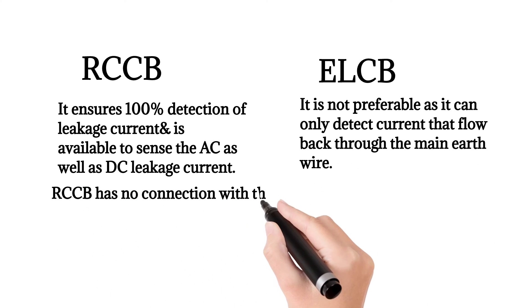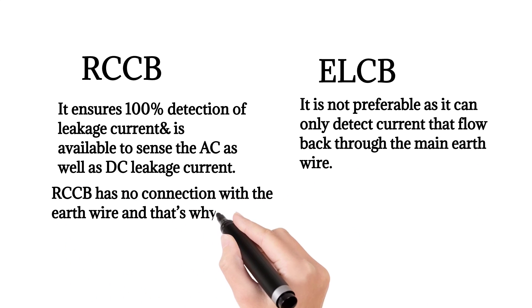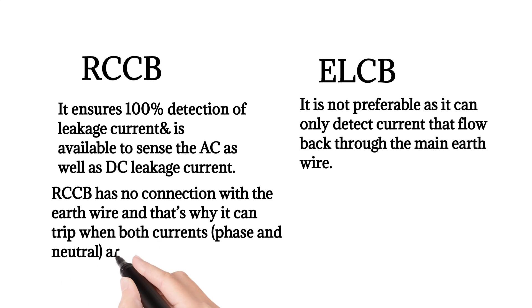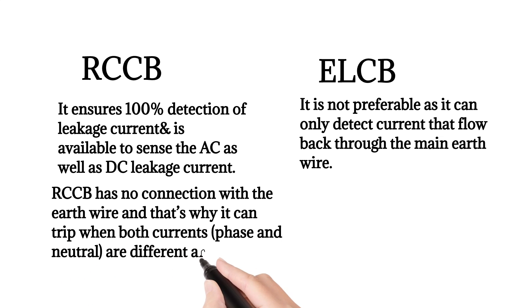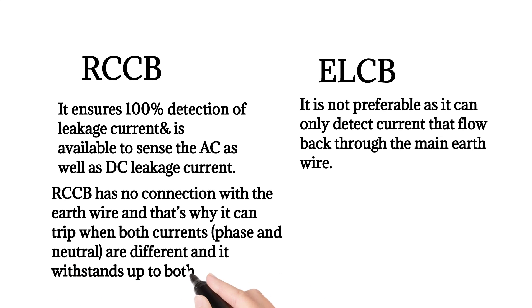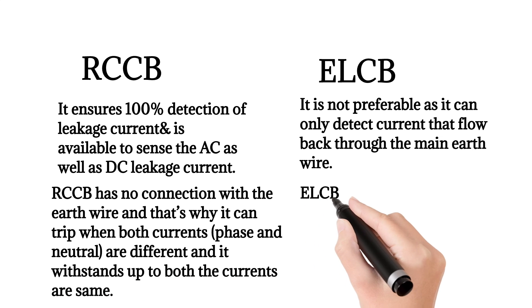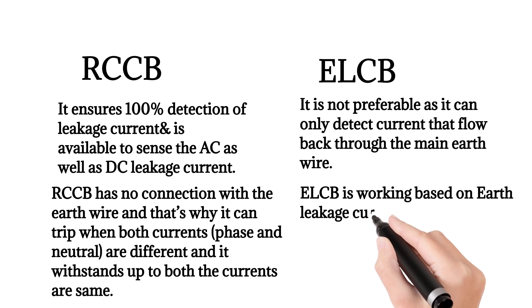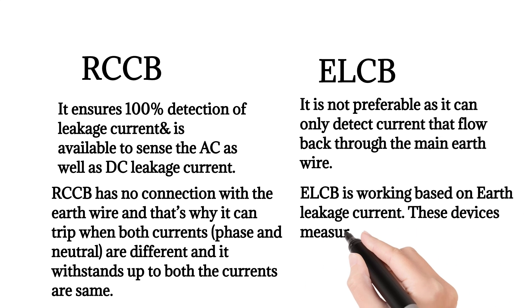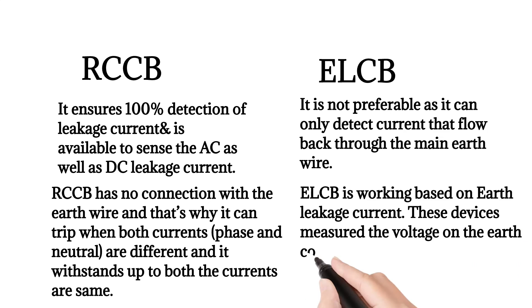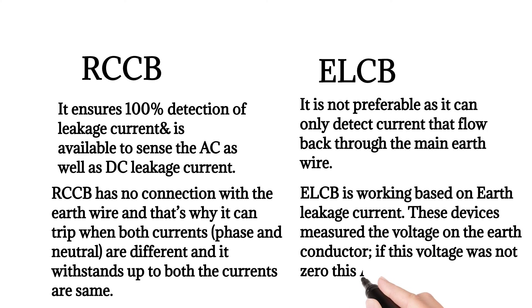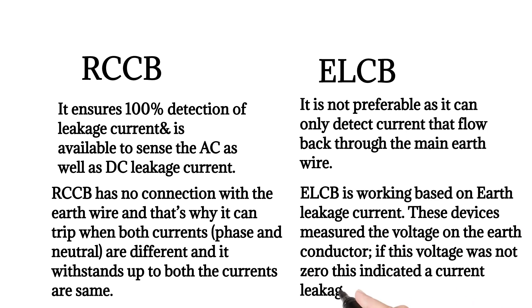RCCB has no connection with the earth wire, and that is why it can trip when both phase and neutral currents are different, and it holds when both currents are the same. ELCB works based on earth leakage current — these devices measure the voltage on the earth conductor. If this voltage was not zero, it indicated a current leakage to earth.